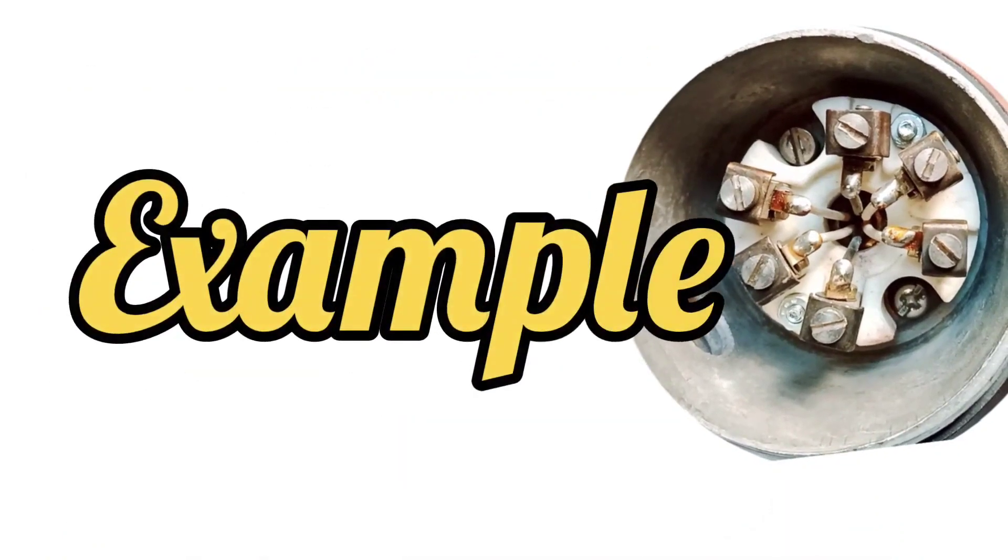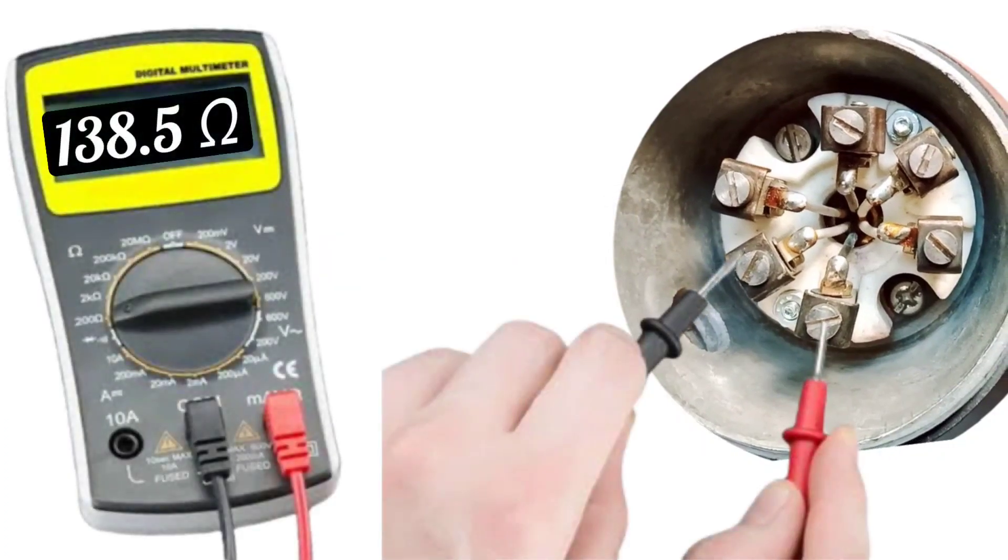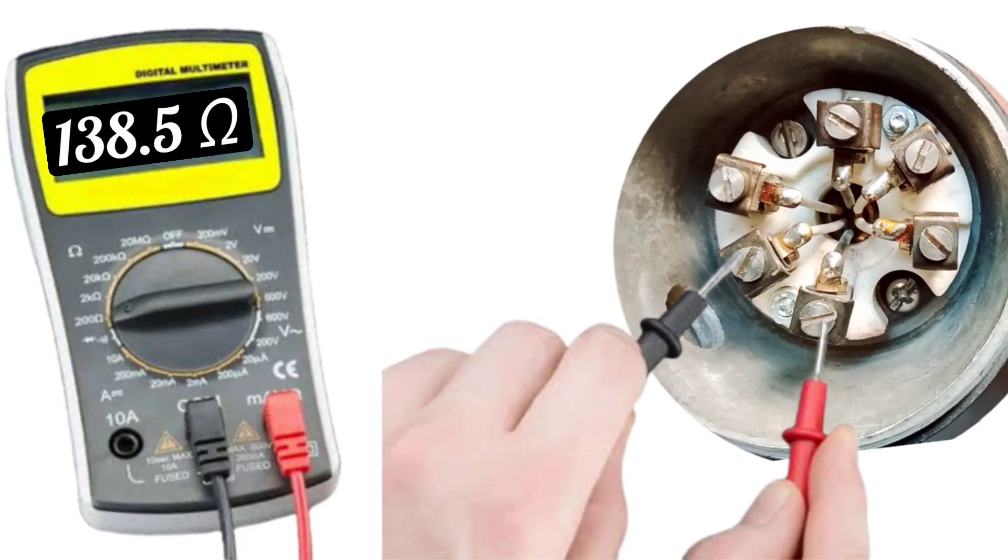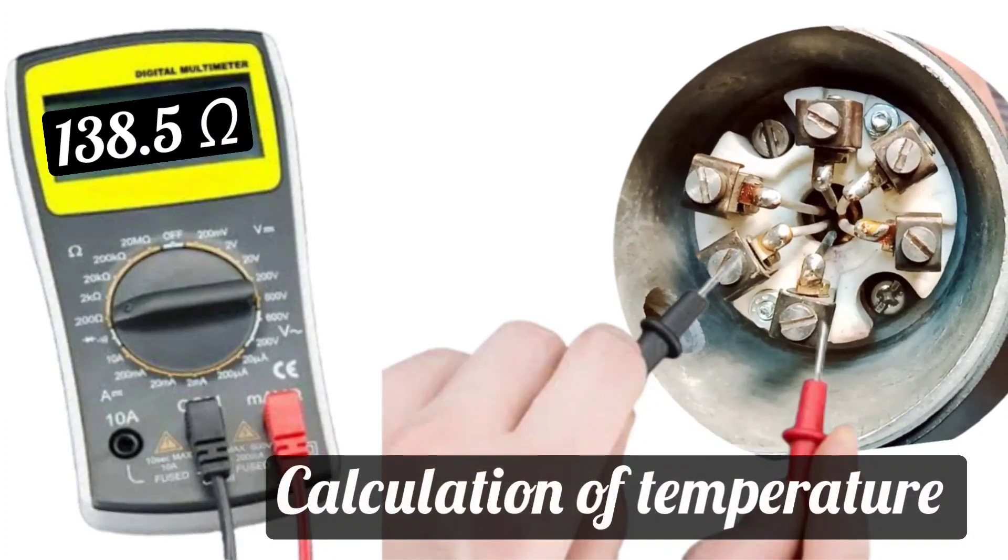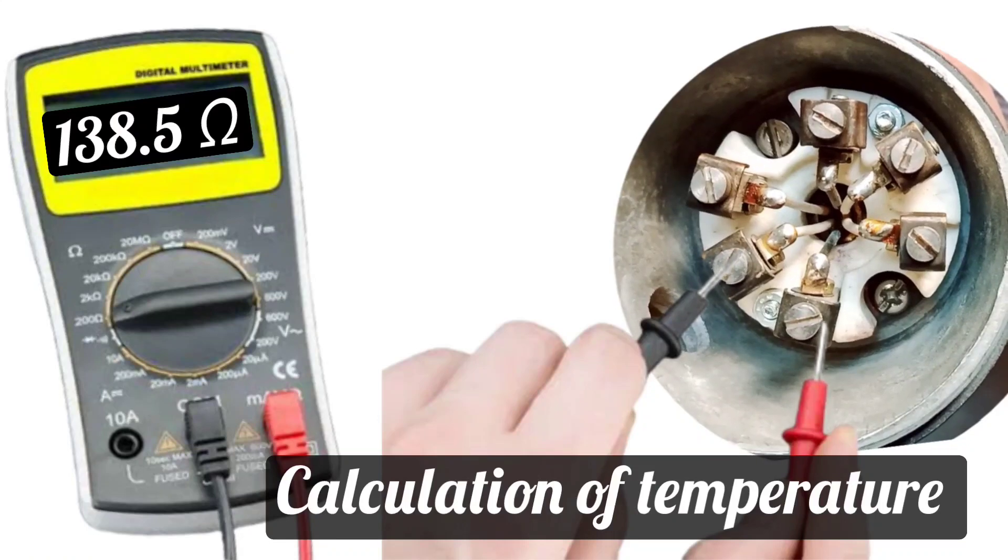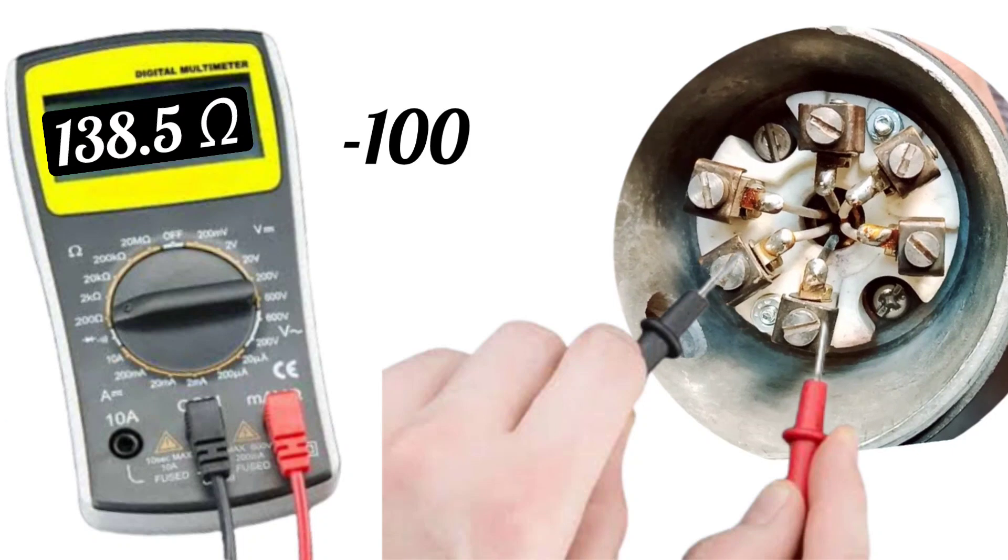Let's understand this with an example. For example, if the resistance of RTD is showing 138.5 ohms, then calculate the temperature. Subtract 100 from 138.5, it will be 38.5.